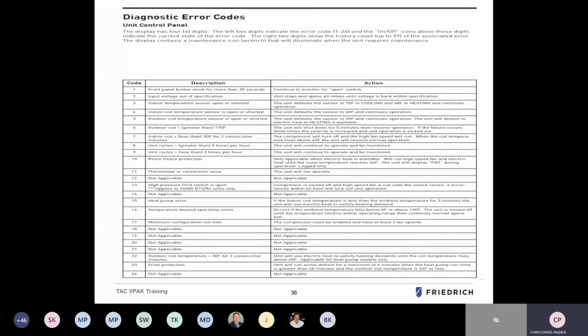Reading from the top, our display has 4 digits. The left 2 digits indicate the actual error code, which is listed here on the left, and a description of the error code related to that number. And then the action or recommended setting on how to correct the error.